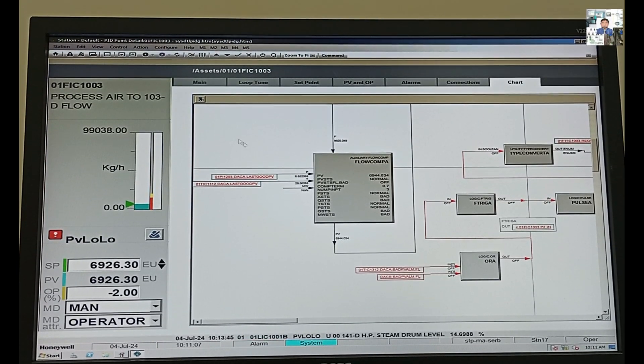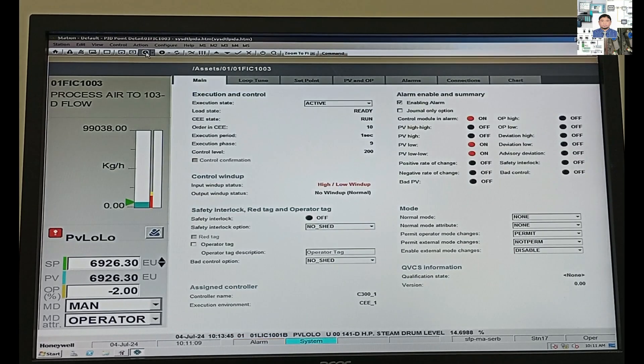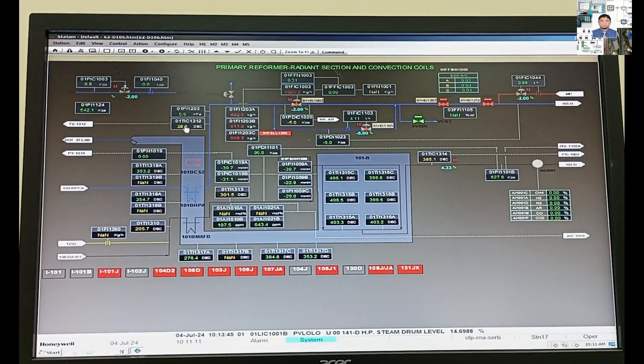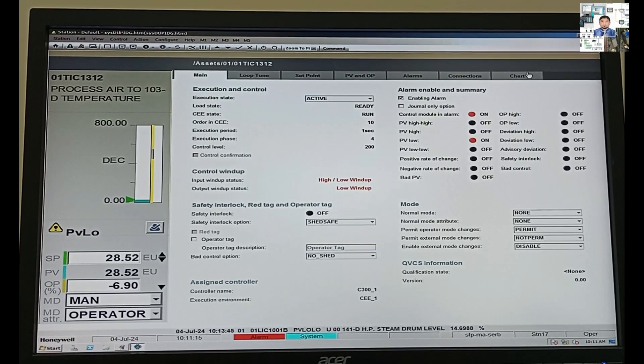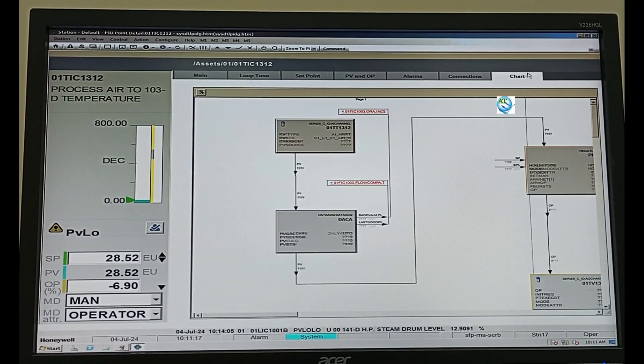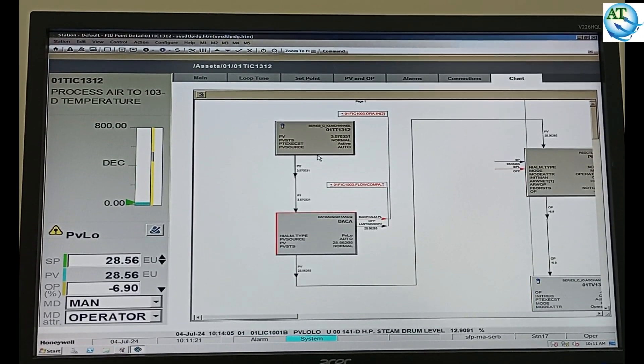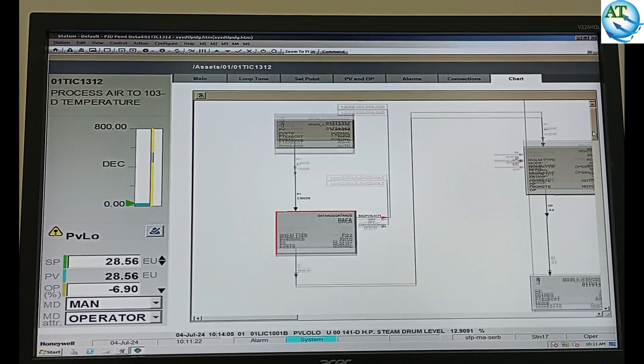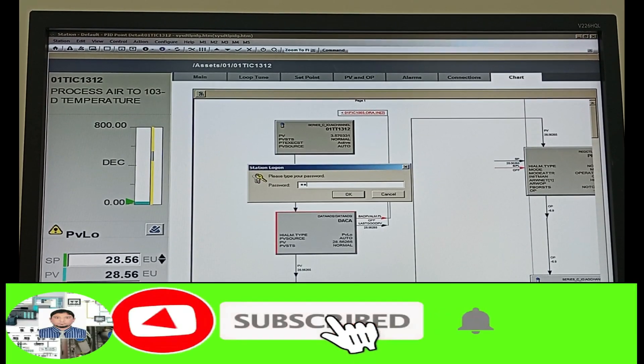We have to replace this one with a new one. We go to that tag and show step by step how we can do this. We open this tag and go to the chart of the logic system. In the logic system, we can do it in two ways: one, you can directly force or go to the man mode in the analog input block; another, you can go to the DACA block. First, we have to go to manual mode.